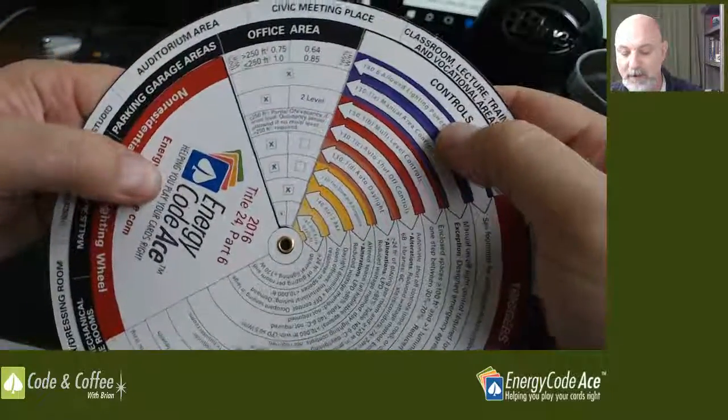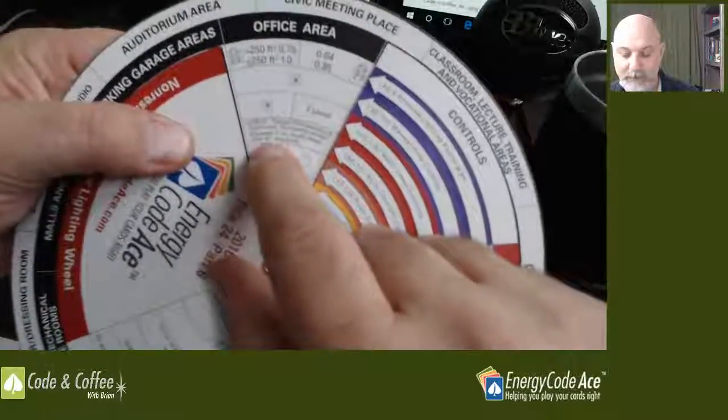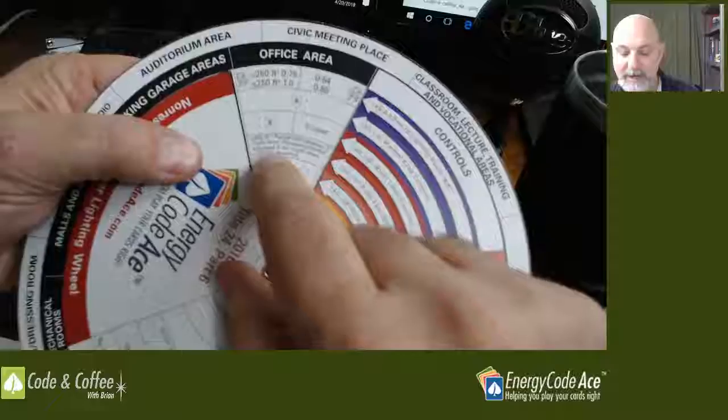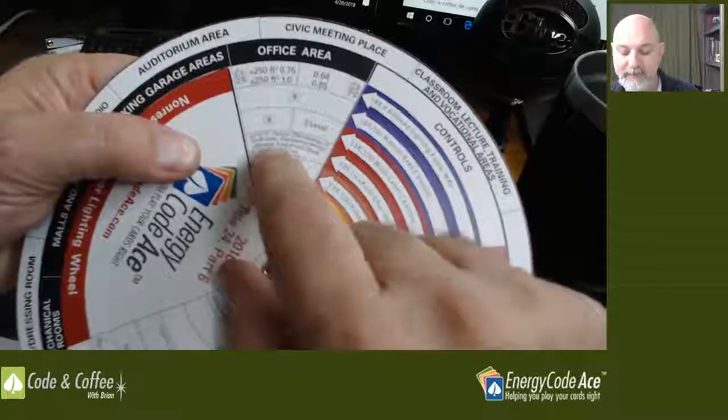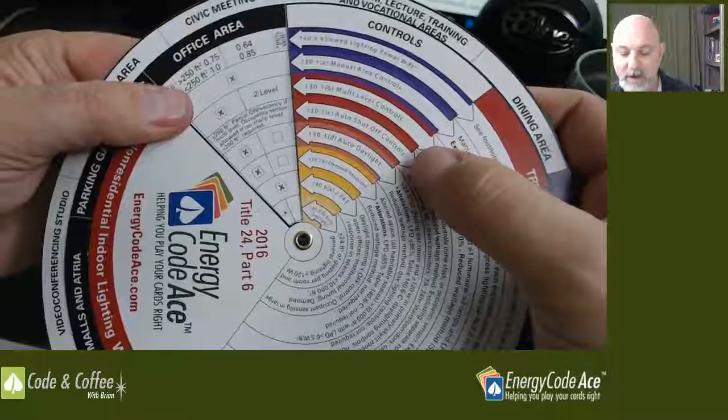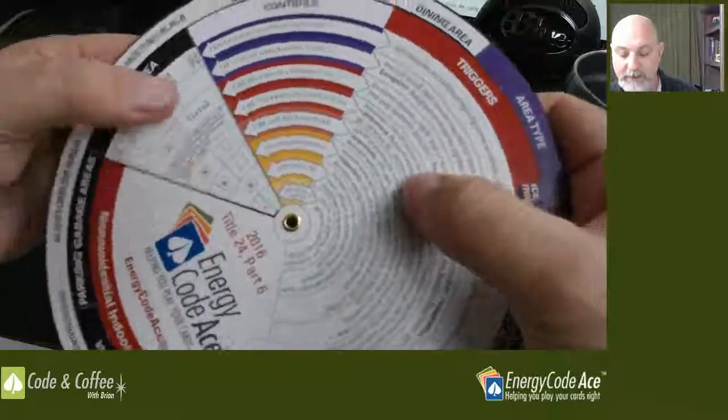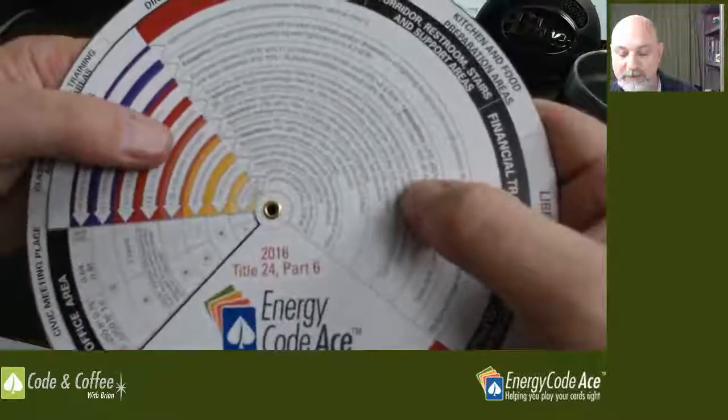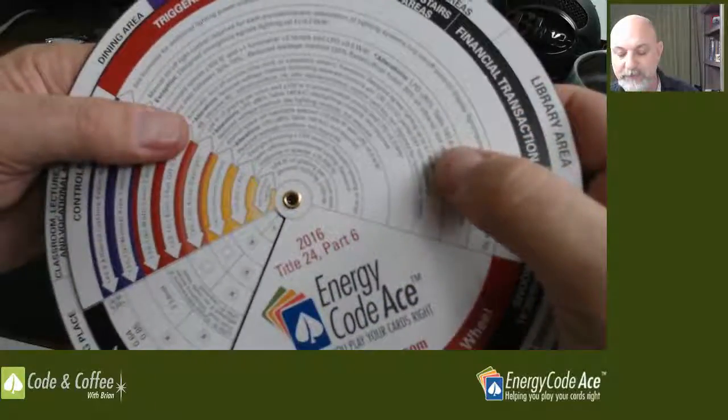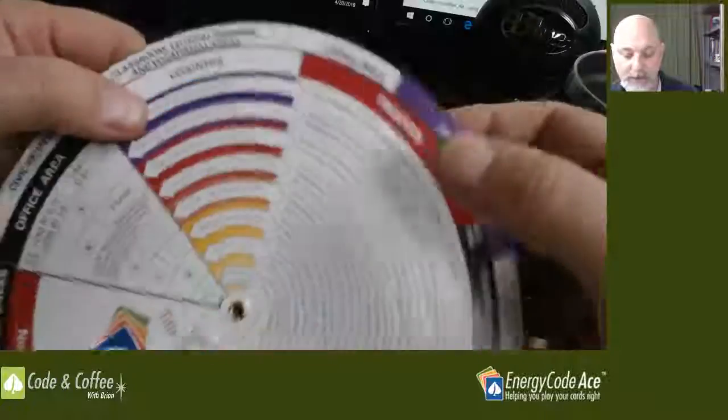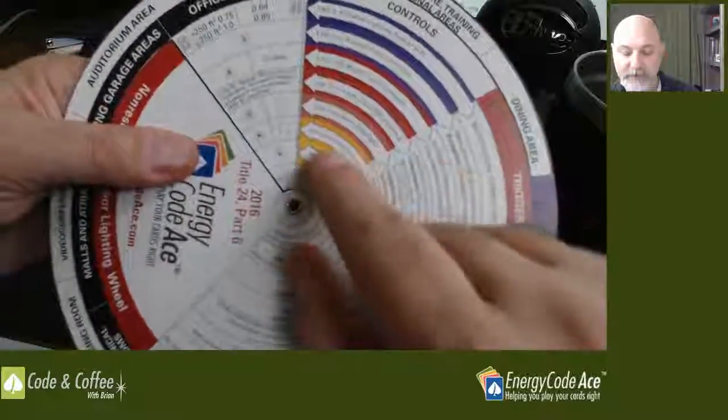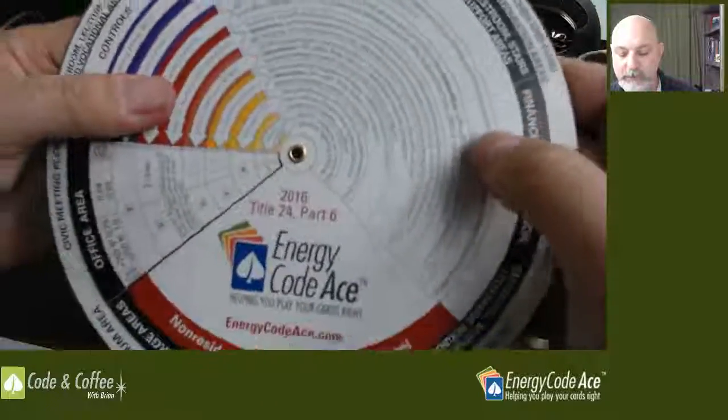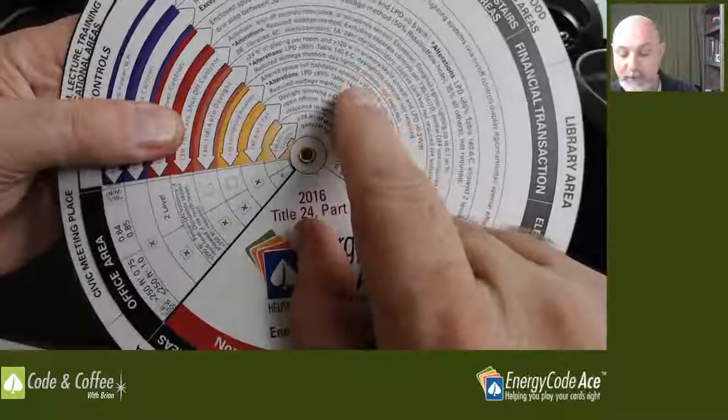Backing up here, auto shutoff controls. You can see, sorry, my camera's not focusing completely here. We're looking at a real close-up. So looking at when partial on vacancy sensor and occupancy sensors required there. You can get into a little more detail. Our next layer is automatic daylighting or daylighting controls, that's required. Here's our triggers. Greater than 24 square feet of glazing per room and greater than 120 watts of primary side-lit zones. And an LPD of 0.3 watts per square foot, greater. Our last layer of lighting controls are the demand-responsive lighting. That is triggered when your building is habitable space greater than 10,000 square foot. That's a mandatory requirement there.